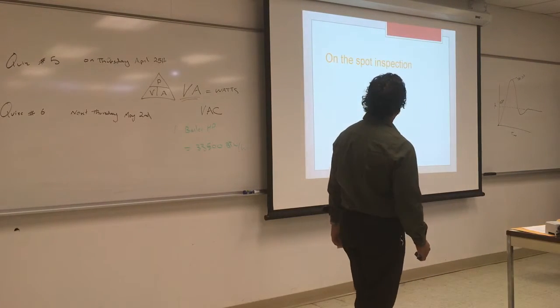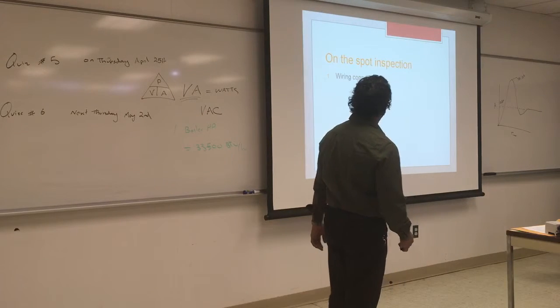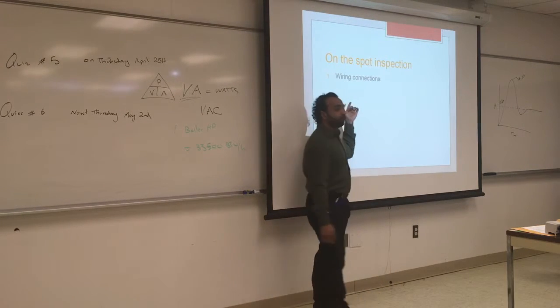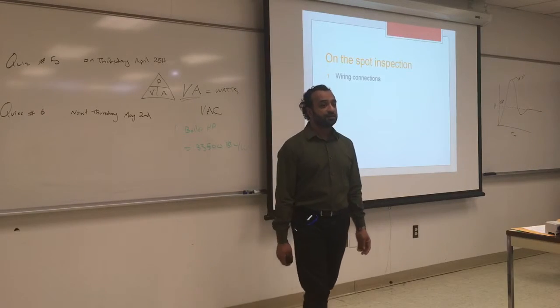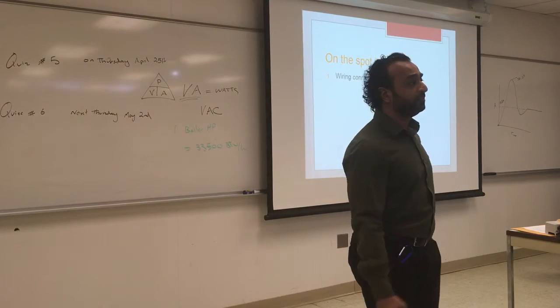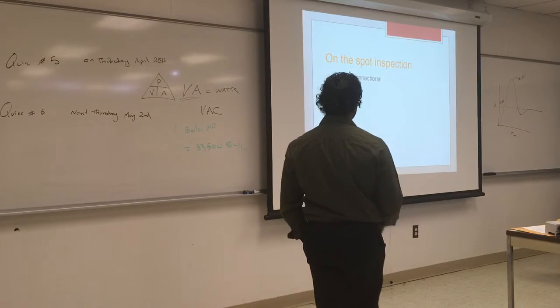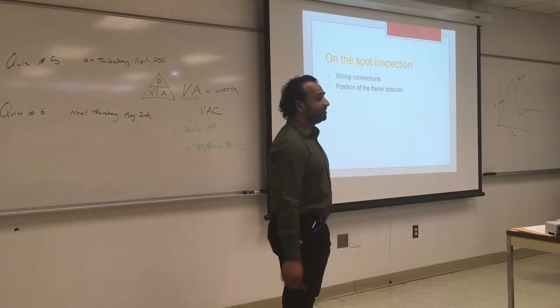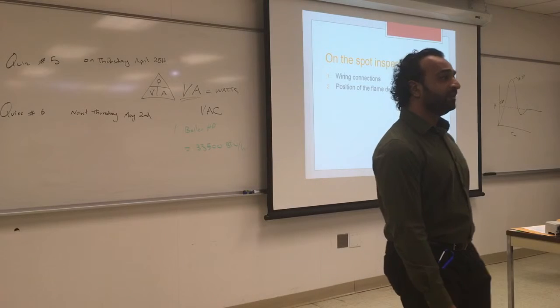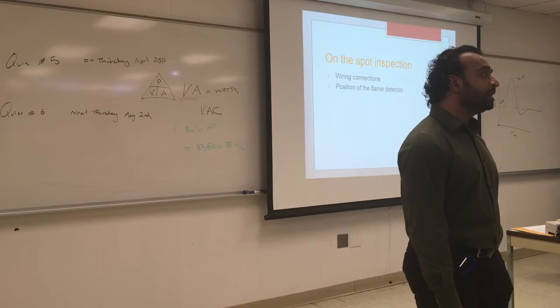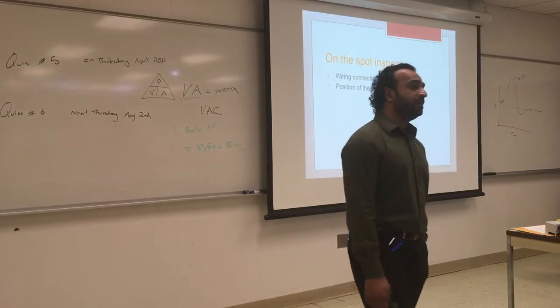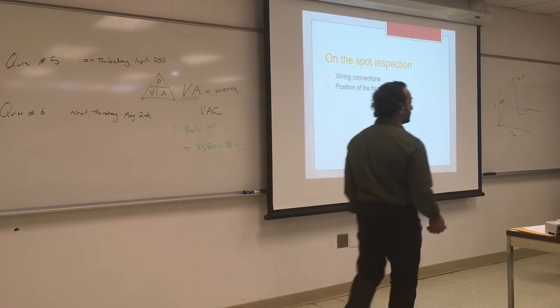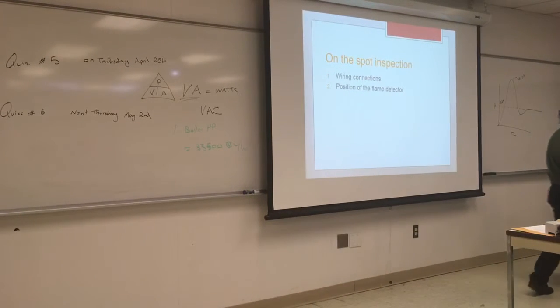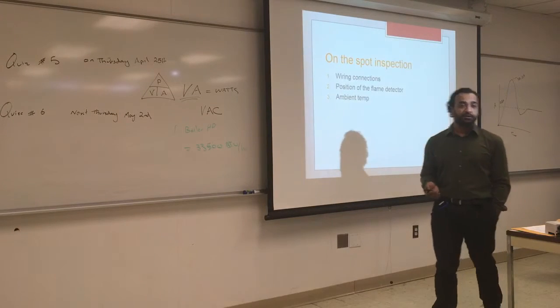Make sure they're running. On the spot inspection, the first thing you want to inspect is the wire connections. If the thing fails, you've got to check the wiring connection, which is very similar to what we do for residential. We check the wiring connection. Position of the flame detector, that is very, very critical. If it's not in the right position, it's not going to work. And make sure no alteration has been made to the base or the holder of the flame detector. Make sure that the place is running in ambient temperature. It's not too hot.